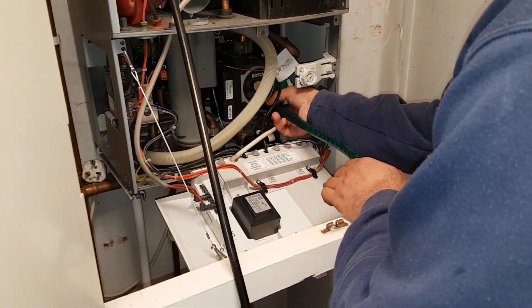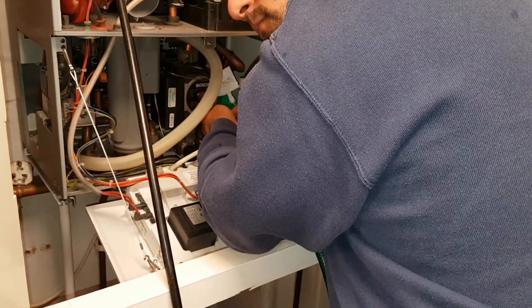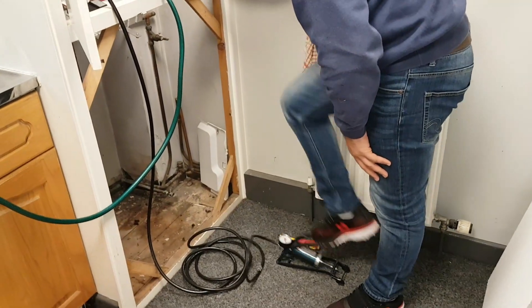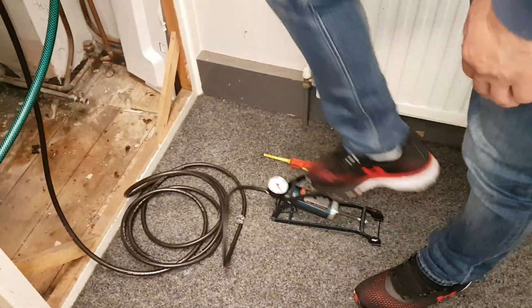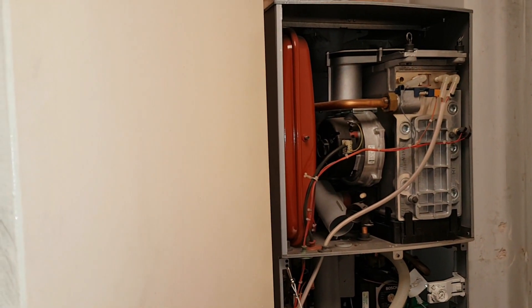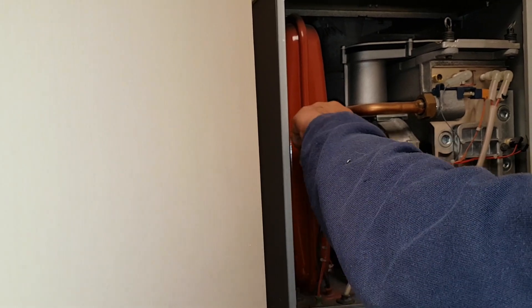Open it — keep your hand on the hose, make sure it's on, and twist it. It's a bit stiff. Now you've done that — we're now at one bar. Good. You can disconnect now. You just took your foot pump off — is that okay? No water — that's right, that's good. That's what you're looking for — a good result.